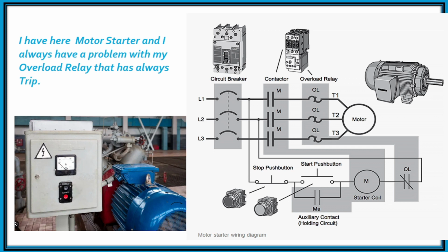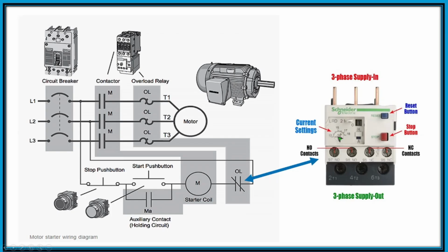I have here a motor starter that I always have a problem with, because my overload relay has always tripped. Do you know how to check an overload relay? This is the overload relay, and to check it using the multimeter, switch to ohms. The 95 and 96 should be closed, and the 97 and 98 should be open. If the 95 and 96 are open even after you reset, that means we have a problem with the overload relay and it needs to be replaced.